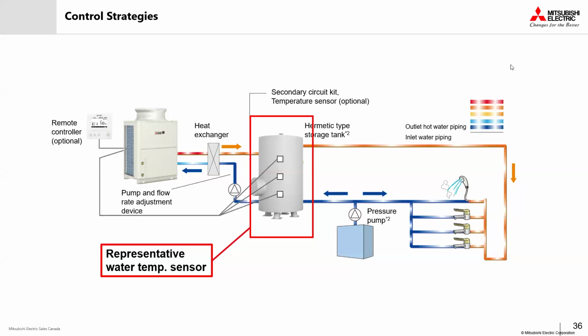So just to take a quick closer look at control strategies with regards to sensor placement. With these low recovery, high storage heat pump systems, we're almost always working with vertical stratified storage tanks, as mentioned. That makes it especially important to monitor the level of hot water within each tank we see here. Placing temperature sensors at strategic points gives the system the information it needs to properly stage our heat pumps on and off, managing that tank charging and maintaining our temperature across the plant. So dialing in the placement of these sensors not only supports consistent hot water delivery and energy efficiency overall, but it also helps the system rely on the heat pumps in hybrid applications as much as possible, which also aligns with those decarbonization goals.